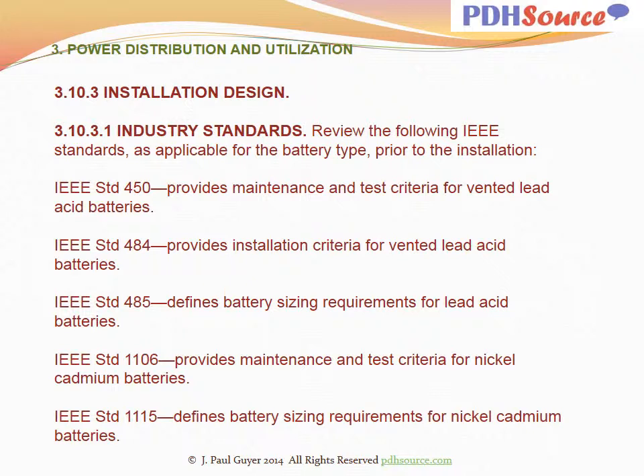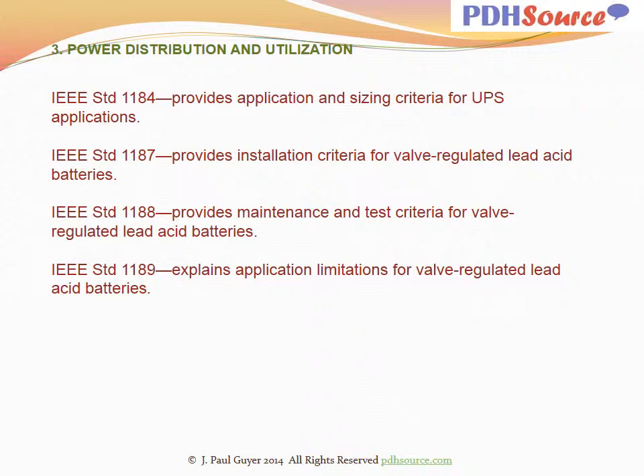Installation design, industry standards: review the following IEEE standards as applicable for the battery type prior to the installation. IEEE Standard 450 provides maintenance and test criteria for vented lead-acid batteries. IEEE Standard 484 provides installation criteria for vented lead-acid batteries. IEEE Standard 485 defines battery sizing requirements for lead-acid batteries. IEEE Standard 1106 provides maintenance and test criteria for nickel-cadmium batteries. IEEE Standard 1115 defines battery sizing requirements for nickel-cadmium batteries. IEEE Standard 1184 provides application and sizing criteria for UPS applications. IEEE Standard 1187 provides installation criteria for valve-regulated lead-acid batteries.